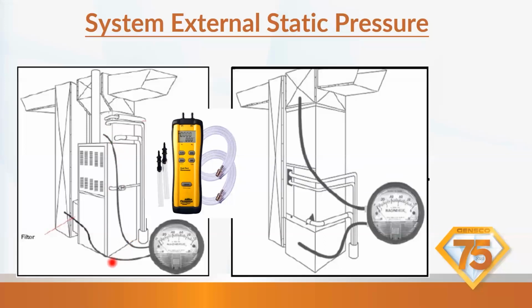So if the coil was down here, downflow, you can put the probe right in the suction line, because that's above the A coil. So you wouldn't have to access the down below. You could actually put it in if you were in downflow position. I hope that makes sense. With the air handler, the coil is installed and rated inside the air handler. So in that case, we can actually go across the full air handler cabinet. With the furnace, we cannot incorporate the evaporator coil. We have to be just the furnace. So keep that in mind.